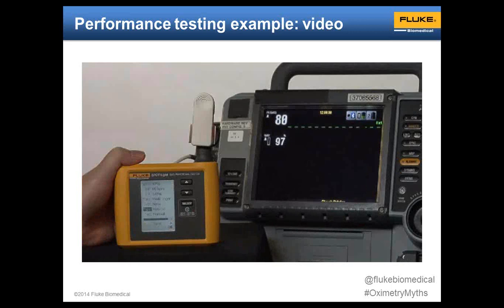We're going to run through a couple of our products. We can SpO2 test with the ProSim 8. This is the only instrument on the market capable of testing the Rainbow Masimo set. It has 8-in-1 capabilities, and we have a pretty substantial amount of evidence that says that we can complete an annual PM in about 5 minutes, including a video that shows that. Fully automated testing: we have a set of preset templates as well as optional PC software and built-in automation.